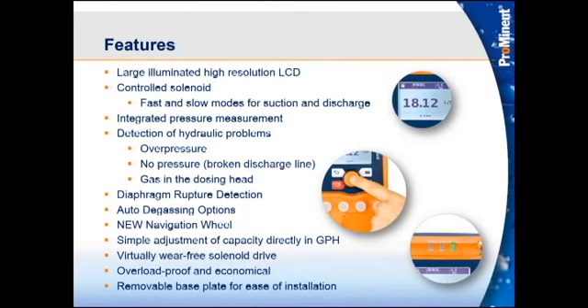Okay. Virtual wear-free solenoid. Really, with the solenoid-driven pump, you only have one wearable item in that solenoid, and it doesn't really wear out at all. Wear on it is very minimal. Our competition, in order for them to get the ability to adjust the stroke length and manipulate how fast and slow that stroke length is, they use stepper motors, which have a lot of gears. They have a lot of bearings in them that are more moving parts that go wrong. Okay, that overload proof bullet point there is kind of going back to the ability to detect hydraulic problems. We do have a removable base plate.